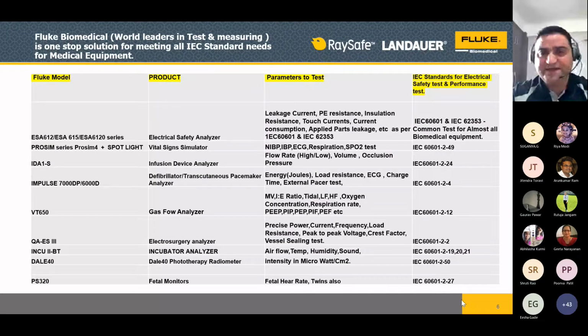It will pass or fail that equipment. If that is working fine, then no problems. If it is not working properly and gives 10 ml in 15 minutes, then you are overdosing a patient. This is why it works like that. Volume, suppose you are giving 10 ml, if it is not delivering 10 ml to the patient end, what will happen? You are not delivering the quantity which is being prescribed. So there is always a problem in that also.